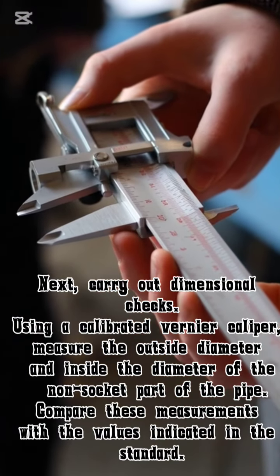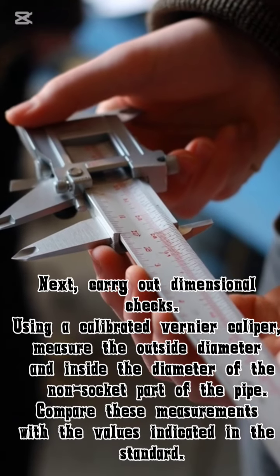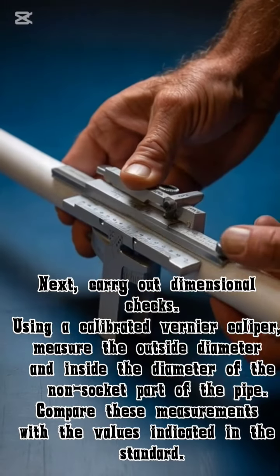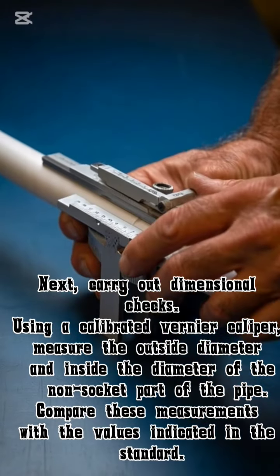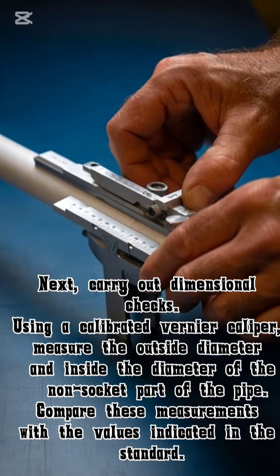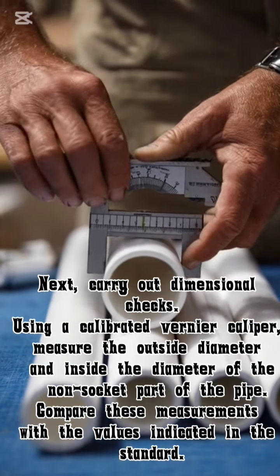Next, carry out dimensional checks using a calibrated vernier caliper. Measure the outside diameter and inside diameter of the non-socket part of the pipe. Compare these measurements with the values indicated in the standard.